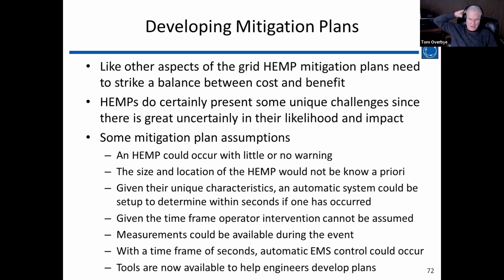Then the trick is to say, well, if this were to occur, if there were an HEMP, what would I do to mitigate it? Like any aspect of grid operation, when you develop a mitigation strategy, you're talking about some sort of protection system. Because of the speed here, it would have to be automated at least to some degree. You have to strike a balance between cost and benefit.